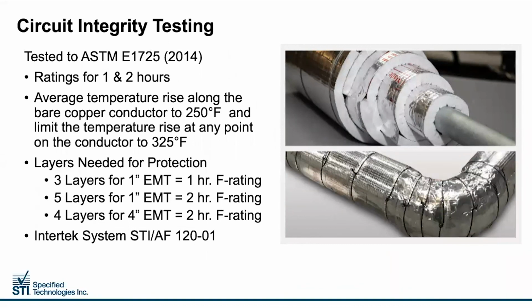We tested EWrap against some of the strictest standards known to the industry. ASTM E1725 is a fire test conducted by an independent third party to determine the efficacy of a shaft enclosure, specifically for the ability of a fire-resistant enclosure to inhibit thermal transmission to the electrical system components within. In order to meet this standard, the thermal sensors placed within the EWrap enclosure must not exceed an average temperature of 250 degrees across all sensors, and no more than 325 degrees Fahrenheit at any one sensor may be registered.